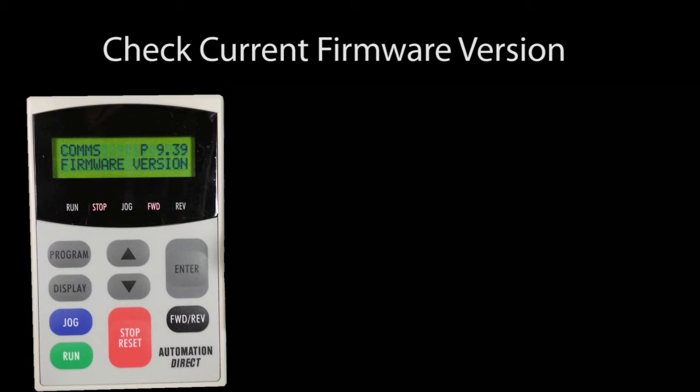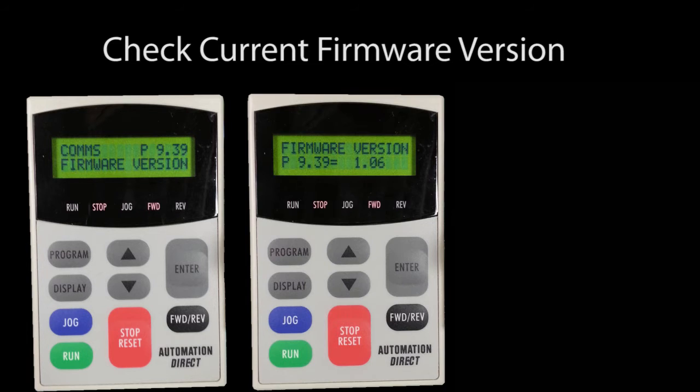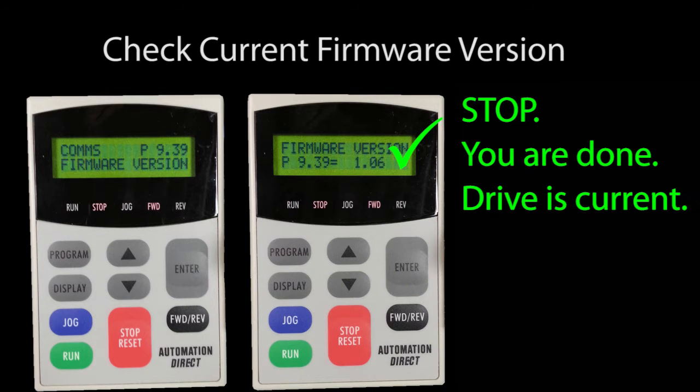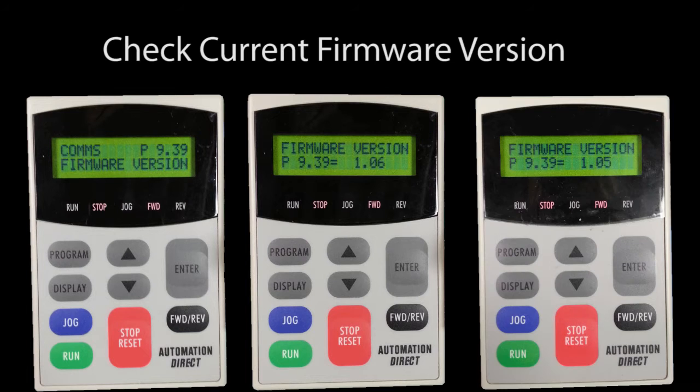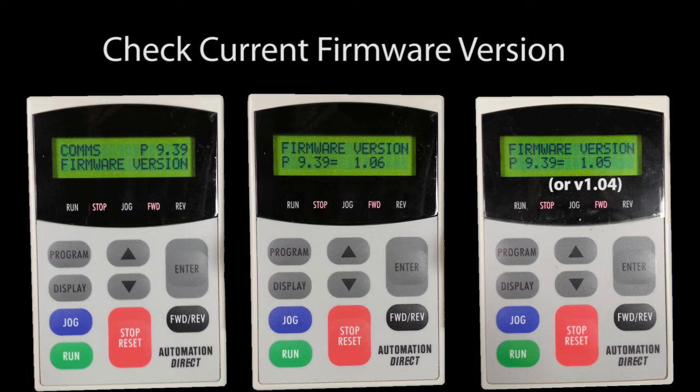Before we get started, turn on the drive and note which firmware version it currently has. That's in parameter 939. If the drive has version 106, then you have the most recent version and you don't need to go any further. If you have firmware version 104 or 105, which is pretty much every drive sold over the last 10 years, then continue on with this procedure.